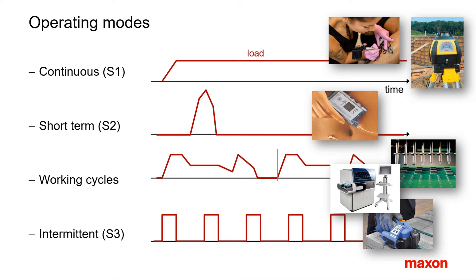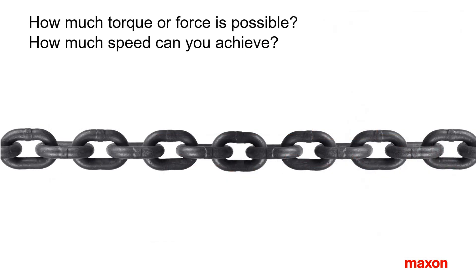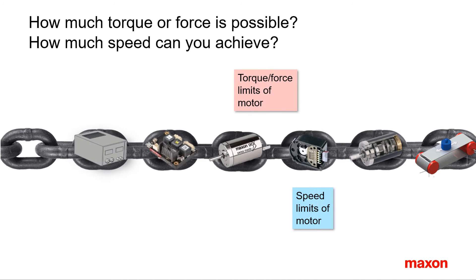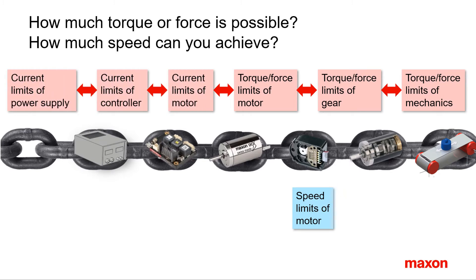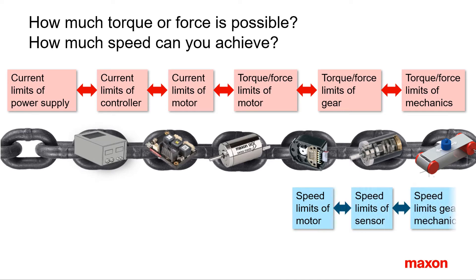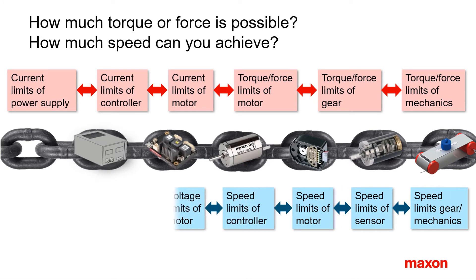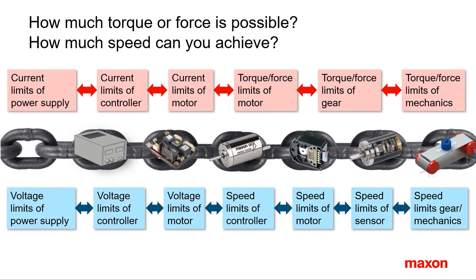Cycles may also vary, as in a strapping tool. On-off operation is a special case of cyclic operation. The weakest link in the drive chain limits the power available at the load. Hence, it's not only the torque and speed limits of the motor — the limited torque capabilities of the gearhead or mechanical system must be considered as well, or the current limit of motor, controller, or power supply. Similarly, the achievable speed can be limited by other components such as sensor, gears and mechanics, or controller.